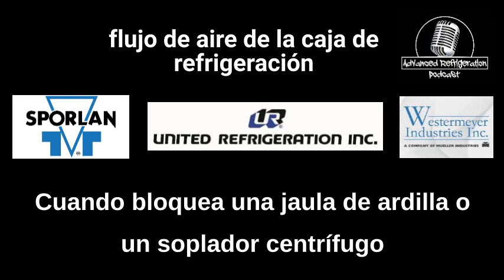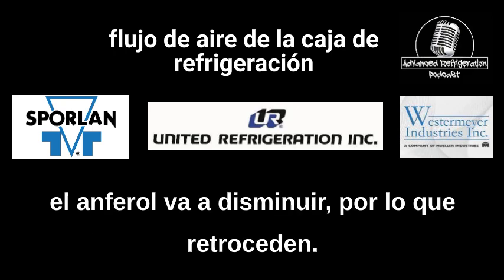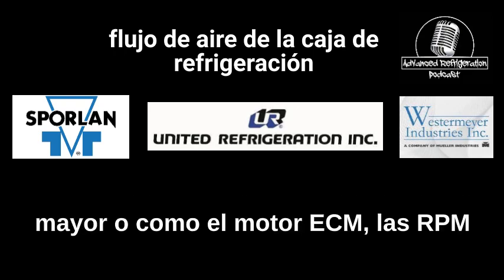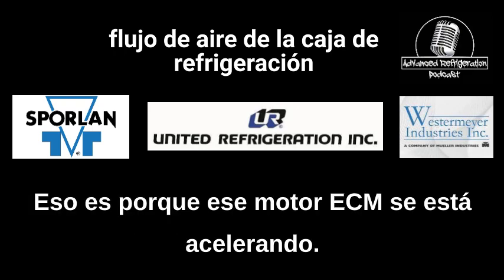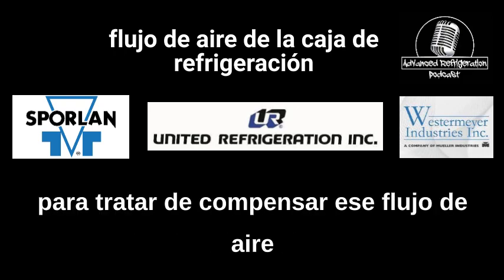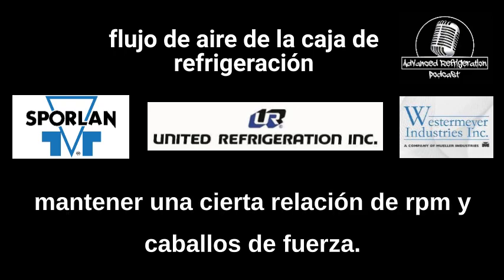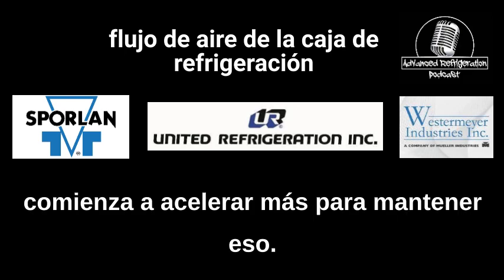When you block a squirrel cage or a centrifugal blower or fan type, your amp draw is going to decrease. So they go backwards. So that's one thing. If you're amping out these motors and they're higher, or like the ECM motor, the RPMs are going higher than what they should be, that's because that ECM motor is speeding up to try to make up for that airflow that it doesn't have, because it's trying to maintain a certain RPM and horsepower ratio. And if it can't get it, it starts speeding up more to maintain that.